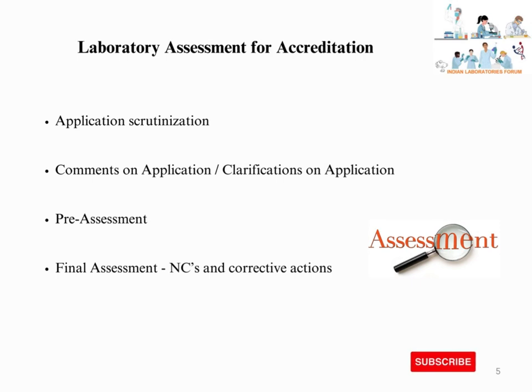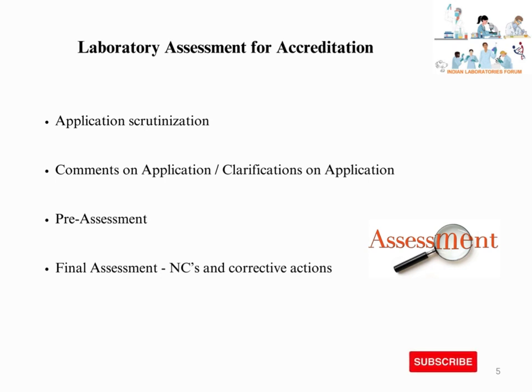Upon submission of the application, the accreditation body will scrutinize it, and if any clarifications or corrections are needed, those details will be communicated to the laboratory for further corrections and resubmission. Upon submission of the corrected application, the accreditation body will plan a pre-assessment — this pre-assessment is optional for most accreditation bodies. If the laboratory is not willing to proceed with pre-assessment, it should provide proper justification to skip it. If the laboratory opts for pre-assessment, the accreditation body assigns auditors who visit the laboratory and provide observations.